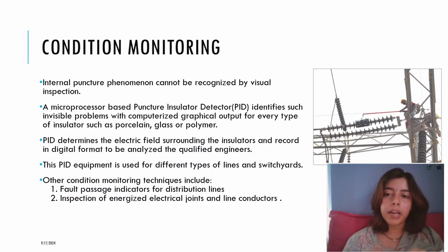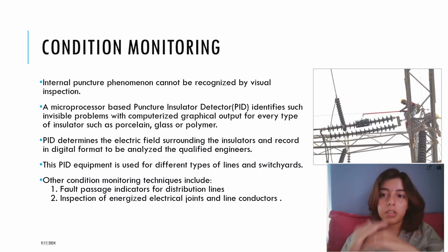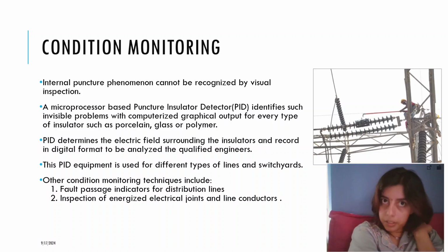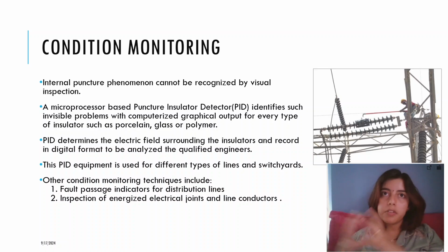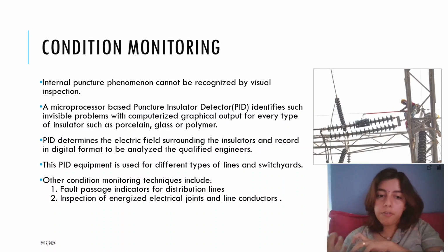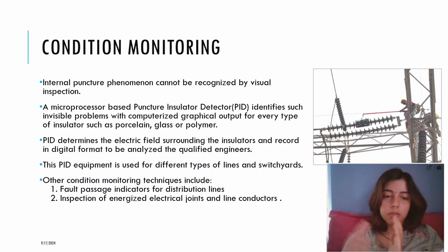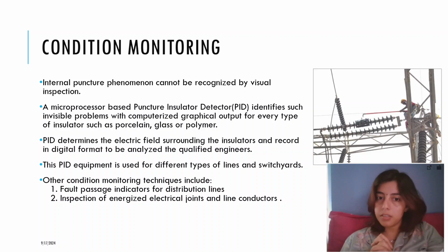This device identifies the electric field surrounding the insulator. Since the insulator is connected through the line, it will not pass electric current through it, but there will be some electric field surrounding the lines. The device determines this electric field and gives an analog input converted to digital form, which is then analyzed by qualified engineers.